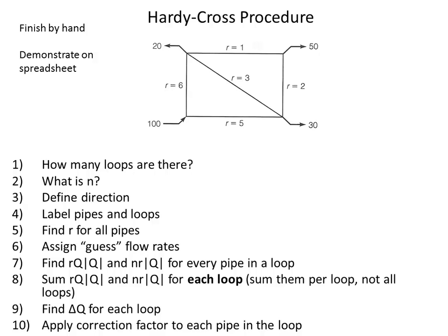All right, so I won't go through all the balancing calculations, but what flow rates should I put in for pipe 1-2, pipe 2-3, and pipe 1-3? Bert, what should be the flow rates that I do for these three pipes? 1-2 should be 25.99. Good. 2-3 should be negative 24.01, and 1-3 should be negative 1.726. Brilliant. That's exactly right. So you have now a feel for how and why things proceed the way they do.